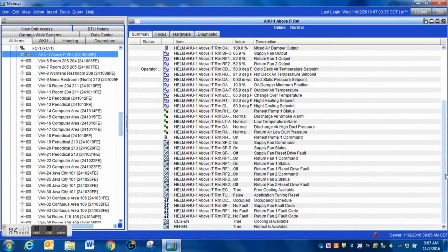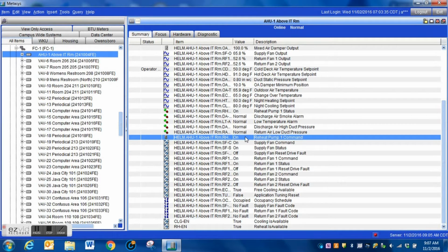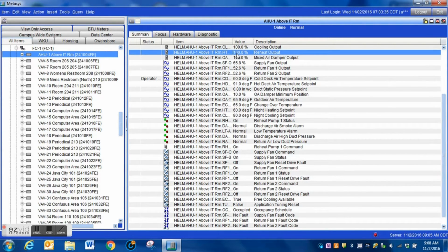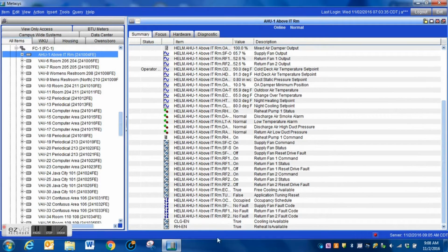The first step in this process is going to be pulling in the main command point for this system. You can see here we have the pump, and we really do not want that pump to run. We're wasting electricity for nothing if that pump is running. And the way this one is configured is when the valve opens, the booster pump comes on.